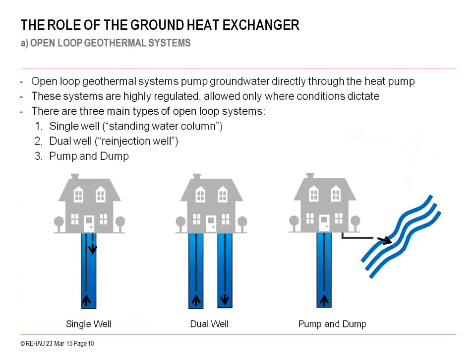On the open loop, we've got single well, dual well, and a pump and dump. What we're doing here with an open loop is using the groundwater from the aquifer and pulling it up into the system. In the single well, you can see we're drawing up groundwater, we run it through the system, and we bring it back down into the same well. Dual well, it's doing the same thing except we're returning the water in a second well. And then the third is a pump and dump. We're drawing water up out of the aquifer and then pumping it into a body of water such as a river.